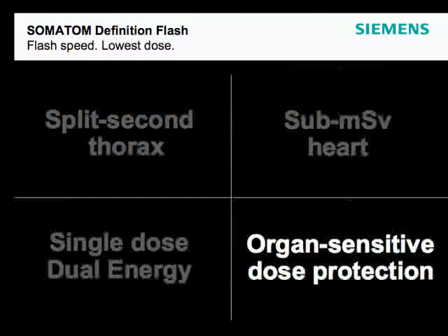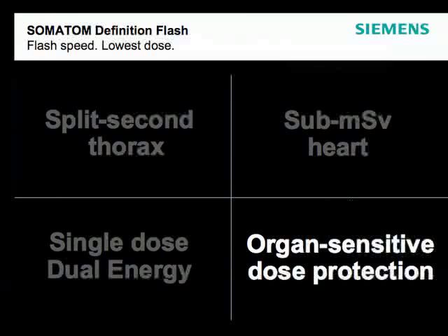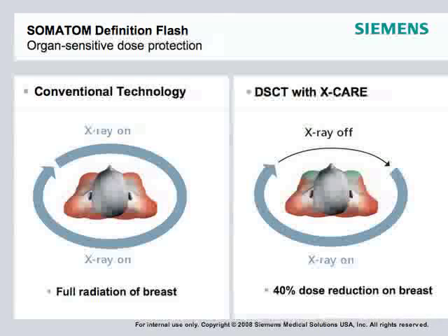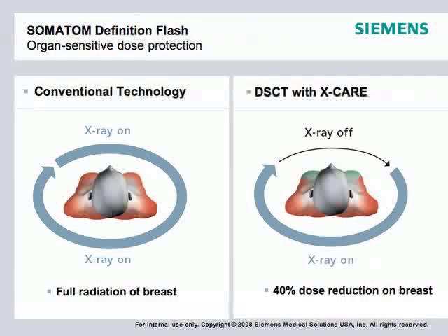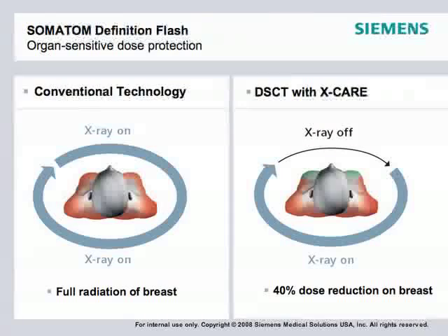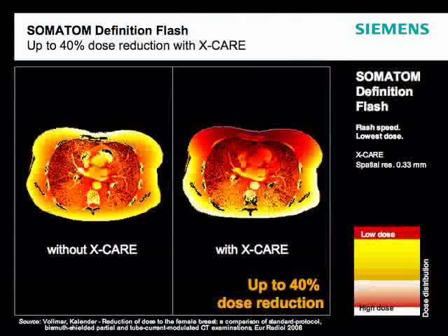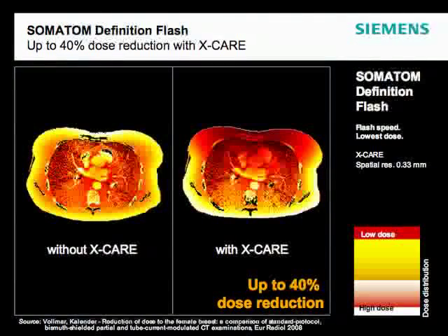Organ-sensitive dose protection is the final key segment. It's important to save dose to sensitive organs including breasts, lens of the eye, thyroid, and gonads. The scanner automatically identifies the scan range, and through selective beam positioning you can reduce dose to specific organs — up to 40% dose reduction in the breast region, for example. Using X-Care with partial scan segments through rotation, dose to specific organs can be turned off. A peer-reviewed article has already been published on this topic.